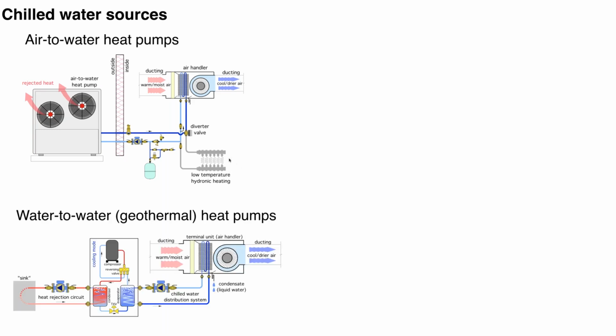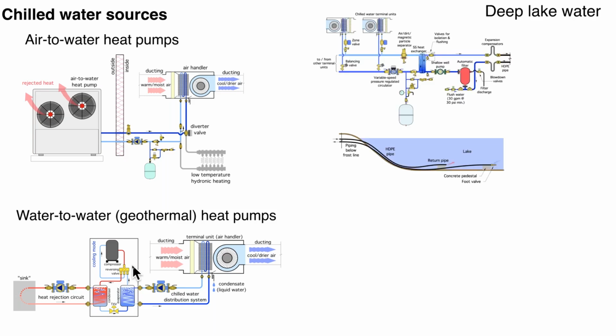And geothermal water to water is another very viable chiller source for these small scale systems. I'm showing it here just going out to an air handler, but we could use the same detail with a diverter valve, and we could take the heated fluid in the wintertime from the water to water heat pump and direct that for space heating. So these are going to be probably the most common sources for the chill water.